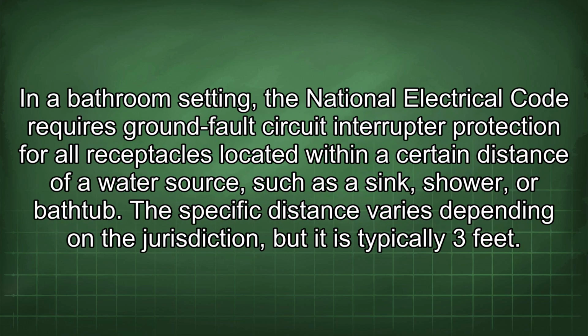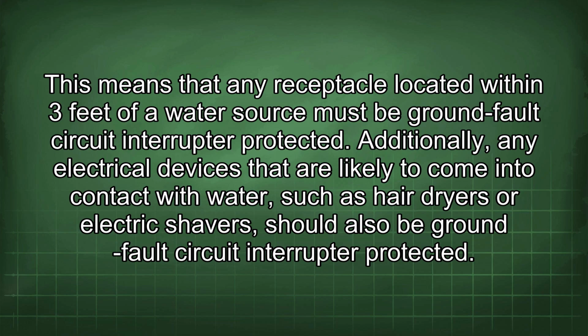In a bathroom setting, the National Electrical Code requires ground fault circuit interrupter protection for all receptacles located within a certain distance of a water source, such as a sink, shower, or bathtub. The specific distance varies depending on the jurisdiction, but it is typically 3 feet. This means that any receptacle located within 3 feet of a water source must be ground fault circuit interrupter protected. Additionally, any electrical devices that are likely to come into contact with water, such as hair dryers or electric shavers, should also be ground fault circuit interrupter protected.